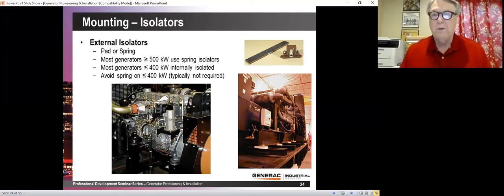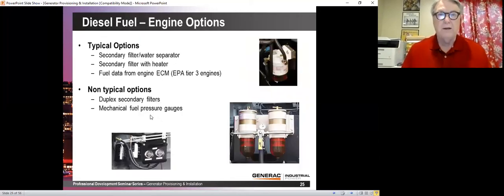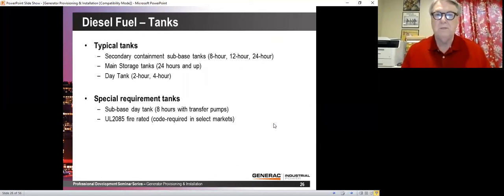If it's a natural gas generator, then of course you could put the springs under the frame. But again, don't do that. Please don't do that. Typical engine options. We've got over here a secondary water filter. That's typical in prime units, a secondary filter with a water separator. And the water comes down here and you can drain it off, and you can actually switch back and forth and drain off the water and actually replace the filter unit while the engine's running because you have a spare. And you can see some other typical options there, but I want to get into more that I think we get questions about.